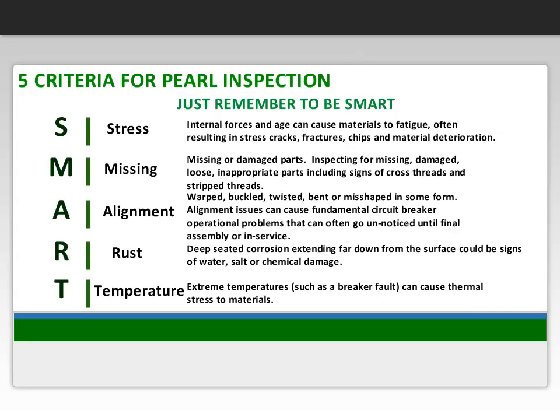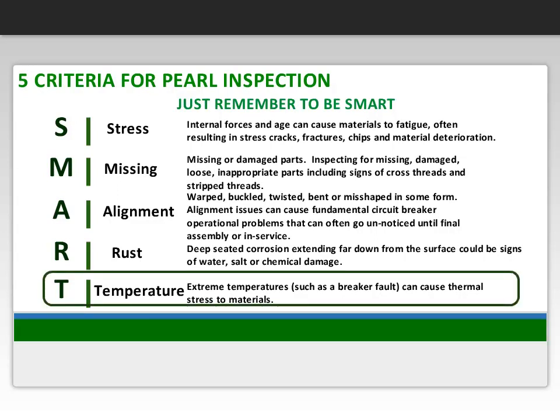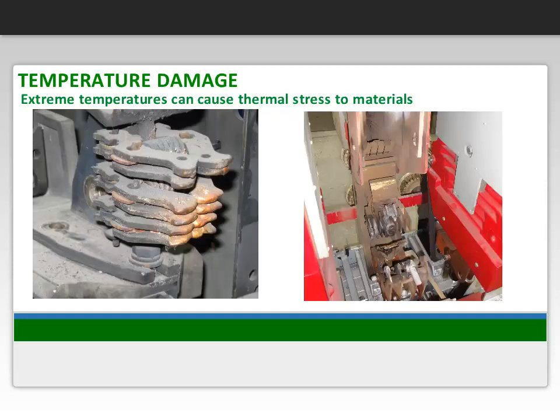The last inspection criteria found frequently throughout the Pearl standards is temperature inspection. Extreme temperatures such as a breaker fault or overload can cause thermal stress to materials. Typical areas to look for this type of material damage is around all current carrying parts, the breaker frame, pole bases, and primary and secondary disconnects. Here are some typical examples of temperature issues. Can you spot them? We will pause again to give you time to examine these images.